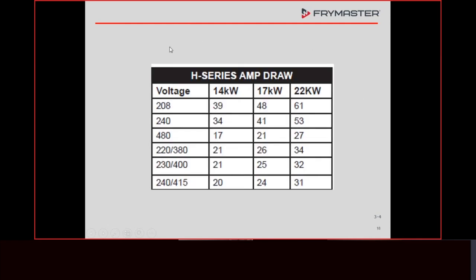This chart just shows you the amp draw on each fryer. If you have a 208 fryer that's 14 kW, which is our most common, it's 39 amps. And so on and so on. Some of these are overseas units and things like that. That's the amp draw. I can tell you, after January of 1997, trying to get a 3-phase amp draw on our fryers is pretty tough, because the terminal block where the wires come in is inside that contactor box, and it's pretty hard to get to. But you can do it.